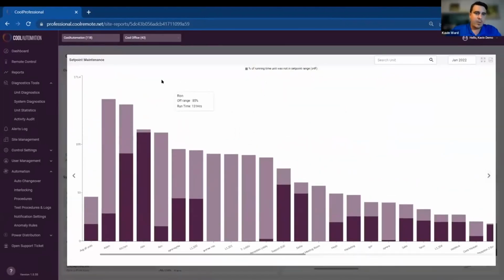And here we can see how well a system is actually able to maintain the set point within 4 degrees. With the bar graph being almost full, you can see that this zone is handling the set point exceptionally well. It's only out of range 2% of the time. Some time out of range is expected. When you make a set point change beyond 4 degrees, that is time that the system needs to heat or cool in order to get within range.